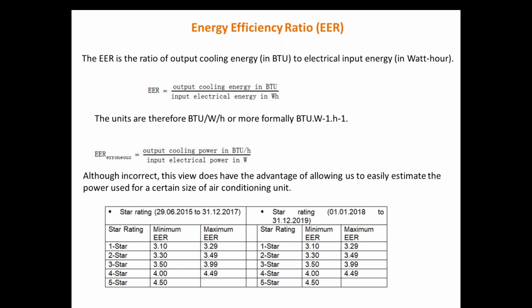So its unit is BTU per watt-hour. But often, by mistake, people calculate EER as output cooling power in BTU per hour divided by electrical power in watt. Compared to the actual definition, this is wrong, but it has the advantage of allowing easy estimation of power use for a certain size of air conditioning, and the value doesn't deviate much. So many people mistakenly refer to EER as BTU per hour over watt, but the actual definition is BTU per watt-hour.